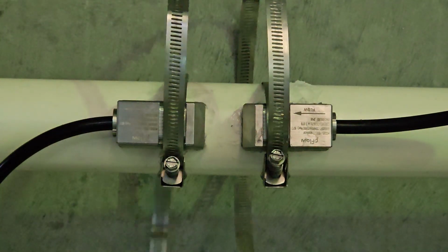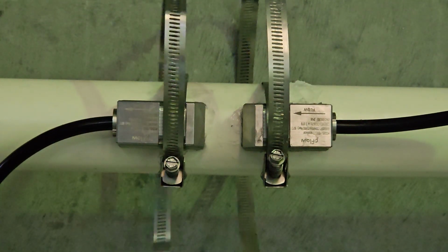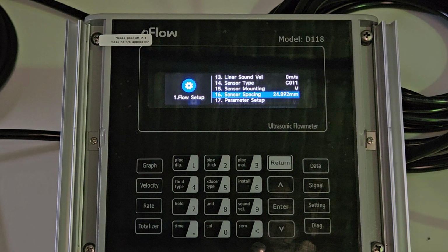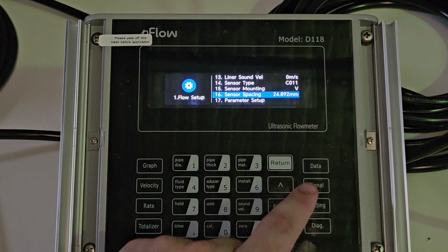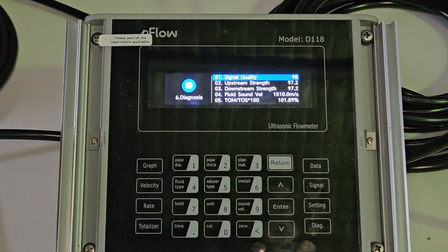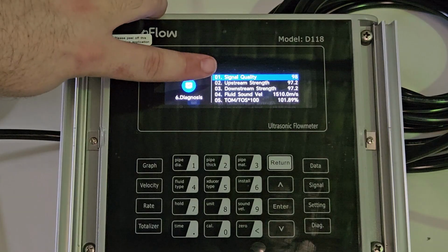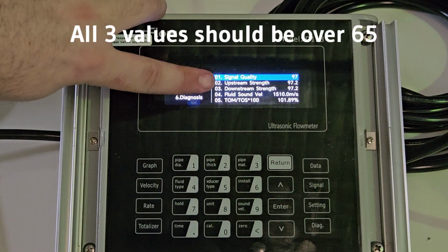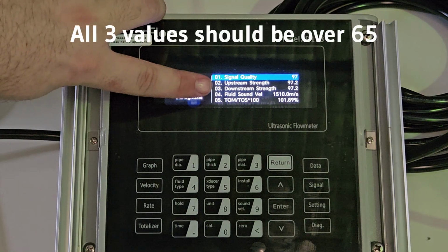If there is fluid flowing through the pipe, soon after everything is set up correctly, the meter should start measuring flow. But there are a few key values you need to check to ensure the meter is working properly. First, press the signal shortcut. You want signal to be as high as possible. Check these 3 values displayed. In general, these first 3 values should be 65 or higher for normal operation.